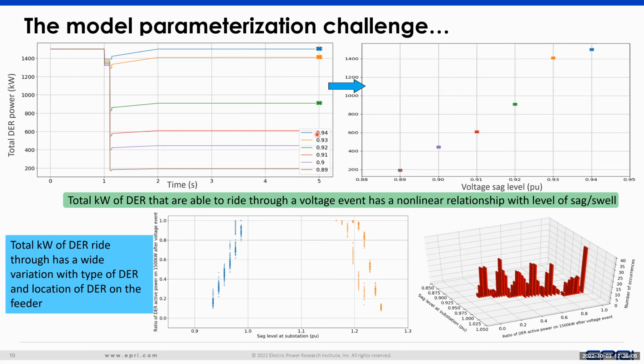So for the blue curve, the voltage during the fault is 0.94 per unit, 0.93 per unit for the orange, 0.92 per unit for the green, and so on. And this plot shows how DER behave in aggregate. So you have the fault being applied here. When the fault is applied, you have the active power output reducing, and then the fault clears. And then you have this wide range of response of the DER. So this fault has cleared. What has essentially happened here for the brown curve is that almost all the DER have tripped, whereas for the blue curve, all the DER were able to recover and ride through the fault.